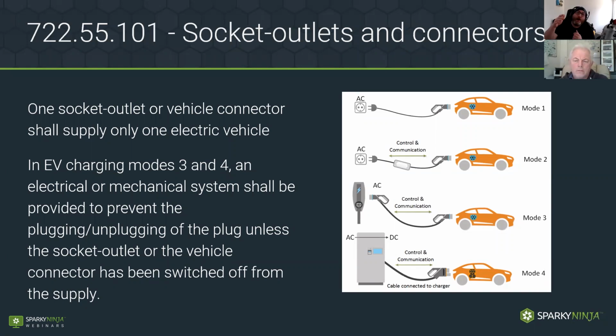Okay. Mode 1 is just a standard plug and socket outlet. That's really not favored. Mode 2 is the lowest we'd like to go, and that's a plug and socket arrangement, but there's control and communication and protection in the lead. That is it. That is as far as it goes with Amendment 1. There's no mention of any extra requirements for testing at all.